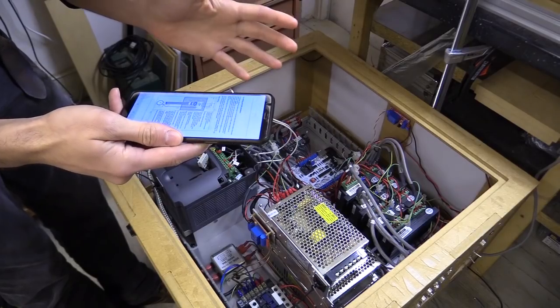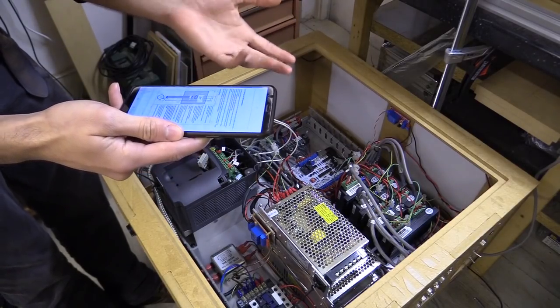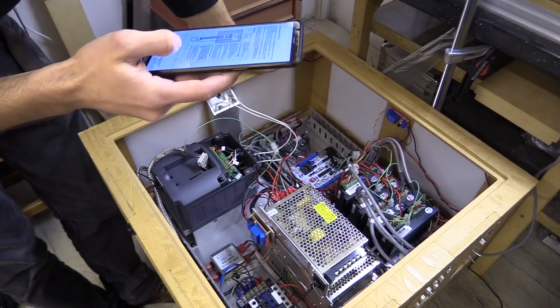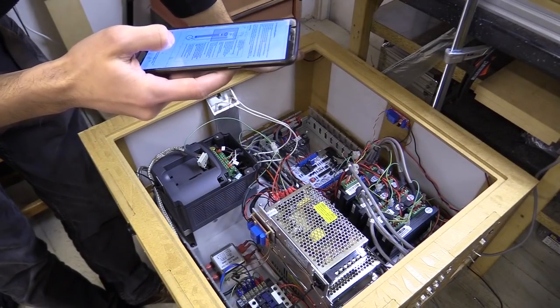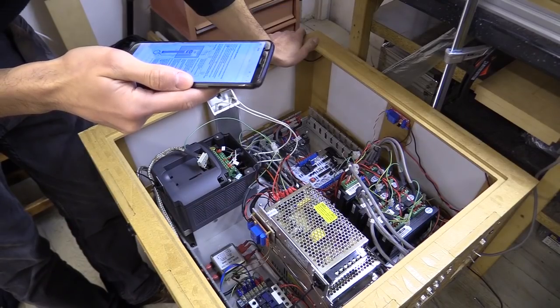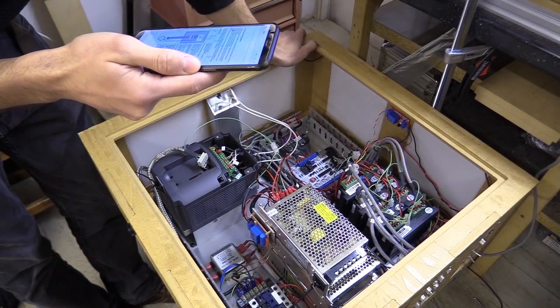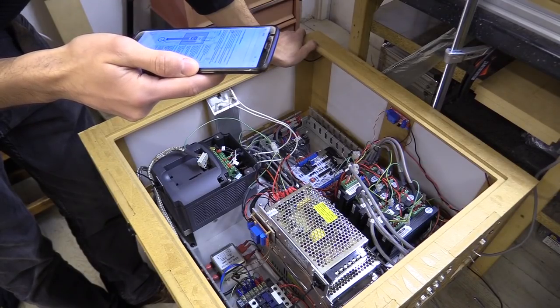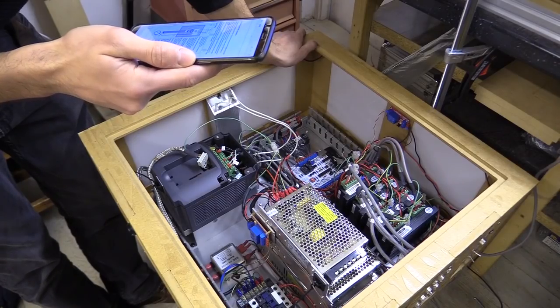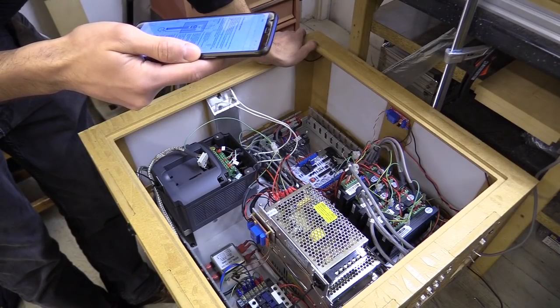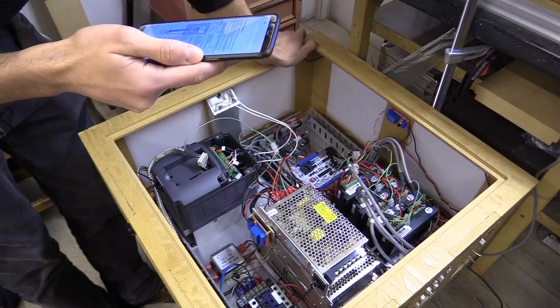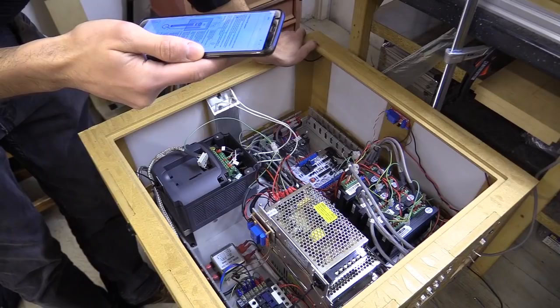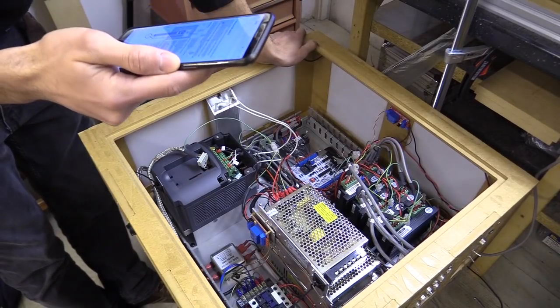On a manual for a different VFD, which is available in the UK from RS Tools, there is one section here about wiring up to the motor, EMC guidelines. To prevent radiated noise motor cable should be put in a metal conduit. Alternatively an armoured or shielded type motor cable should be used. For effective suppression of noise emission the cable armour or shield must be grounded at both ends to the motor and the inverter ground. I was told that you should only ground at one end, and that's really confusing me.